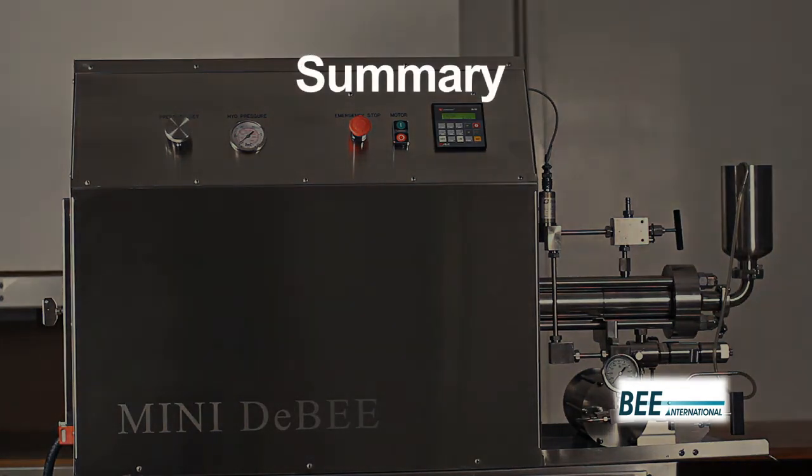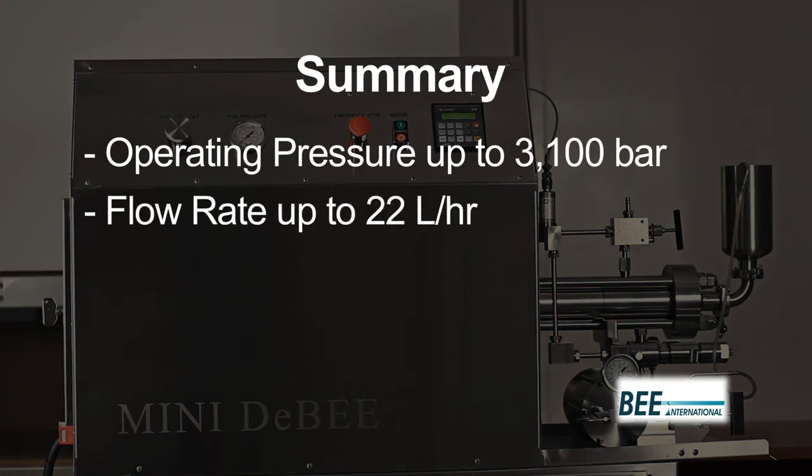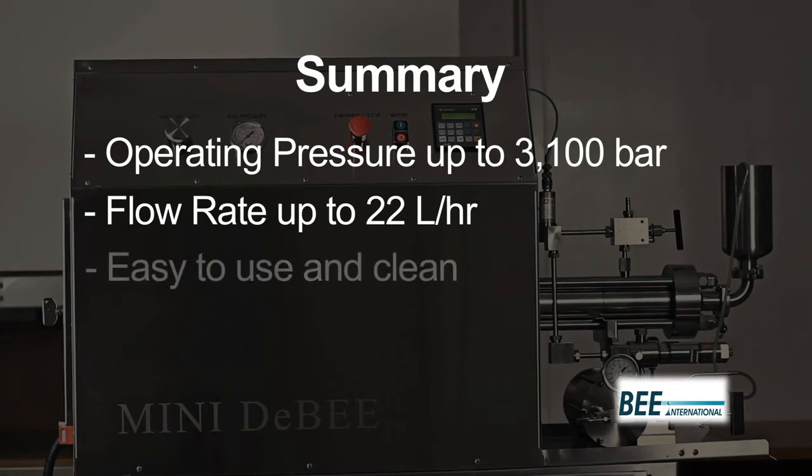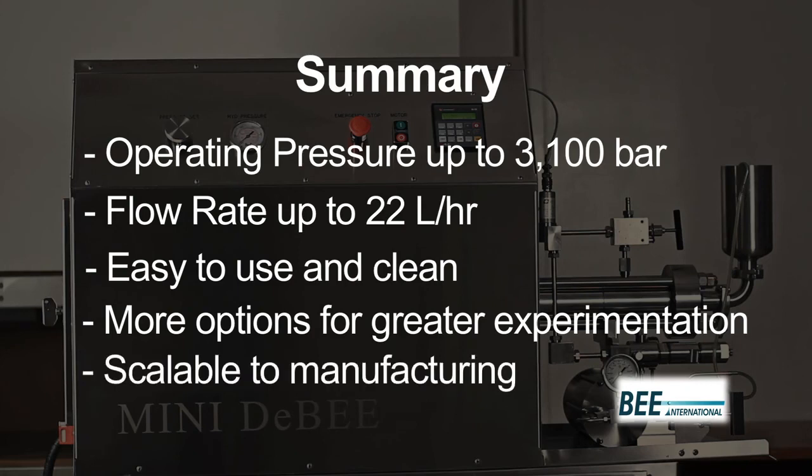In summary, the Mini DeBee has an operating pressure up to 3,100 bar, a flow rate up to 22 liters per hour, is easy to use and clean, has more options for greater experimentation, and is scalable to manufacturing.